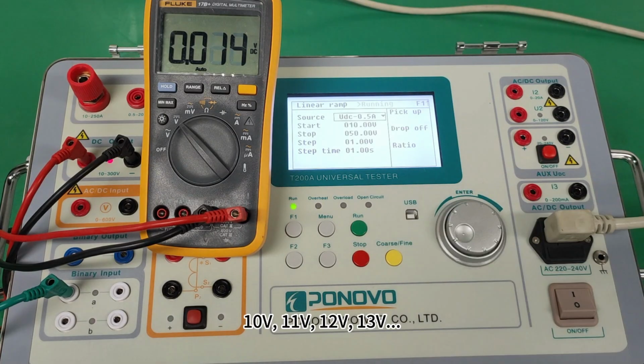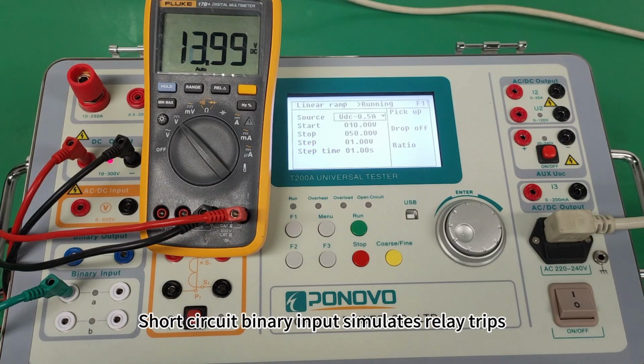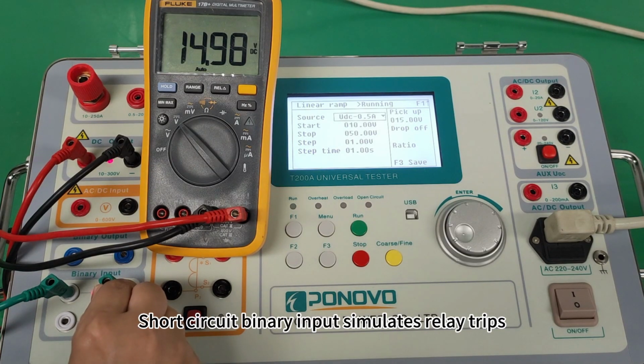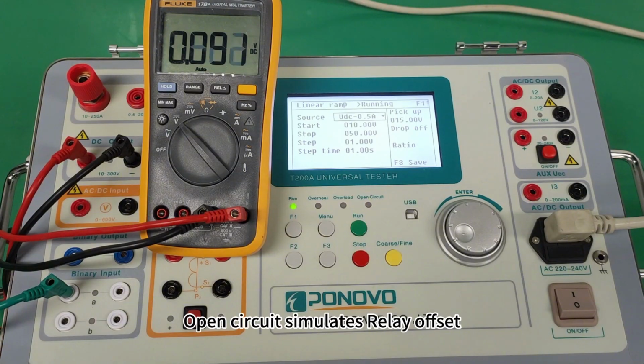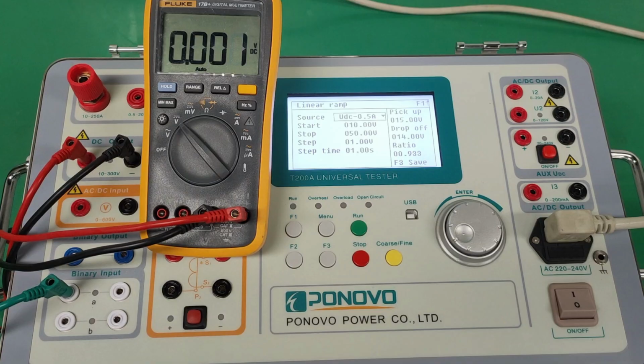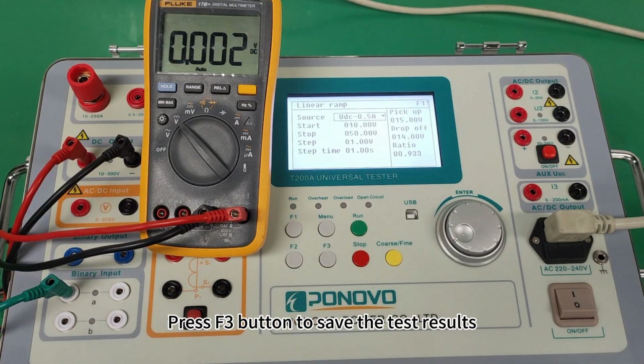Press run button. 10 volts, 11 volts, 12 volts. Short circuit binary input simulates relay trips. Then begin to drop. Open circuit simulates relay offset. Here comes test results. Press F3 button to save the test results.